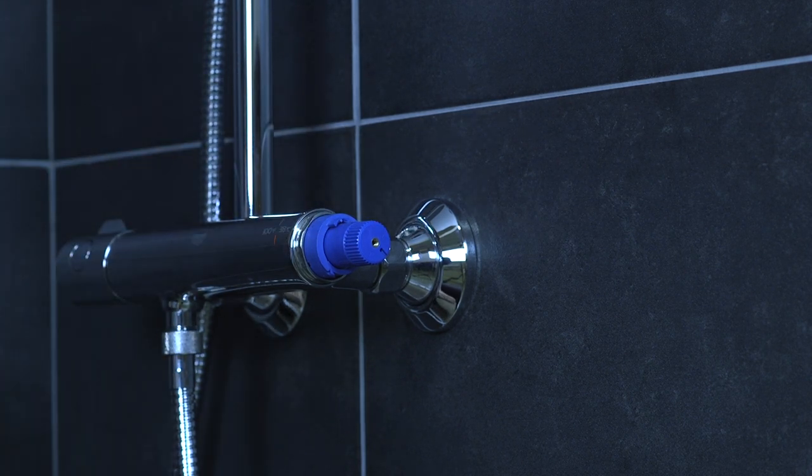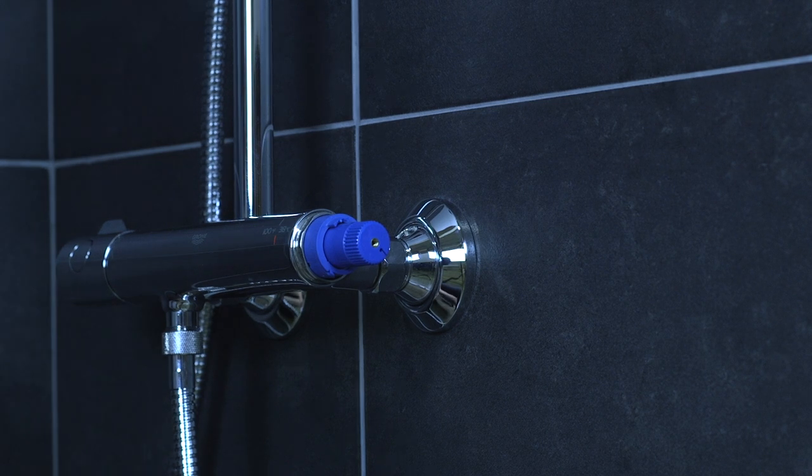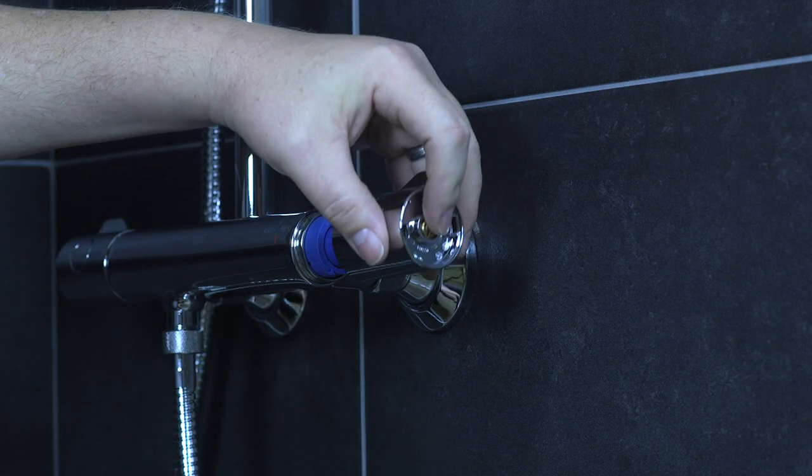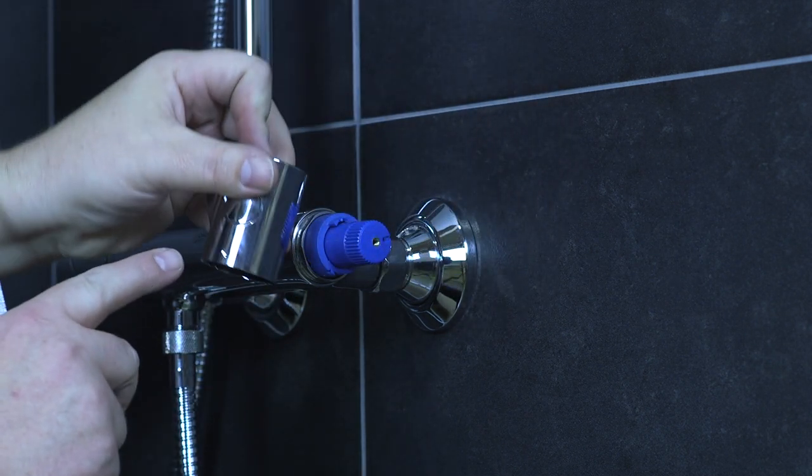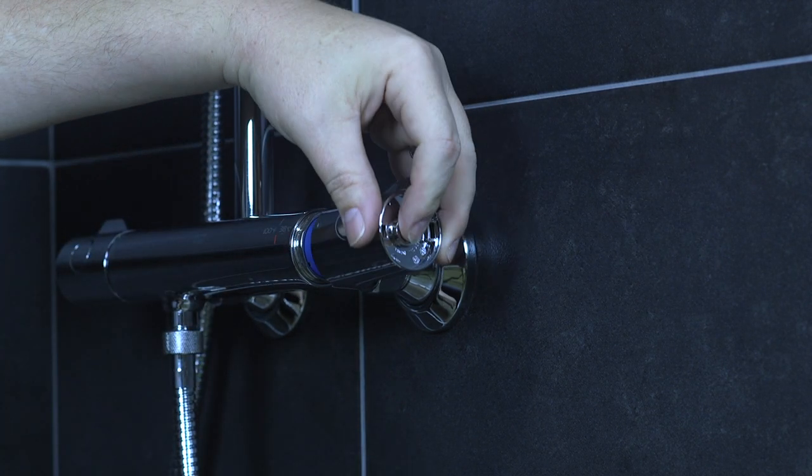At this point you could turn your hot and cold on. Being it is a thermostatic unit, you would have to go ahead and calibrate the unit. Once you get a hundred degrees of water flowing, just put your handle on and line up the little dimple with the hundred degree marker on the front of the valve.